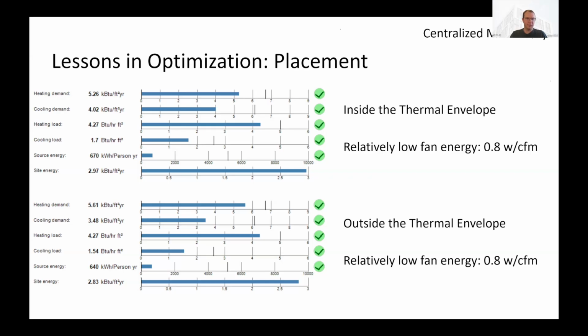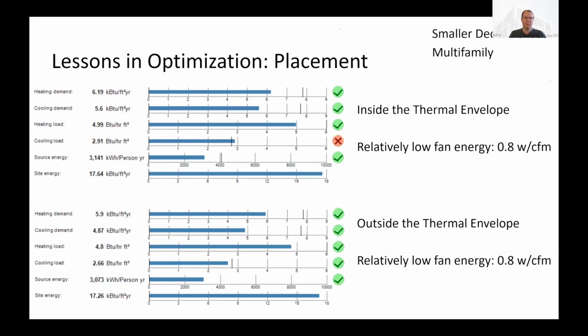And in this case, inside the thermal envelope has a little bit of additional source energy required. So it's worth noting that the cooling is going up faster than the heating is going down, and that moving this ERV outside of the thermal envelope reduces that cooling demand and load and reduces the total source energy. This does change a little bit, anyway, depending on the type of project. So in a smaller decentralized multifamily, we're seeing some of the same things.